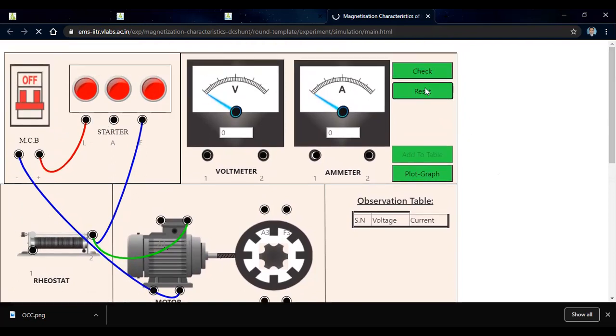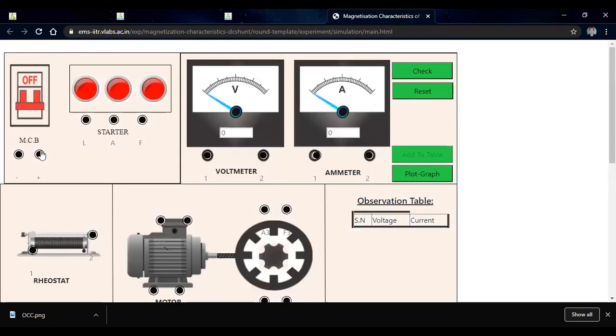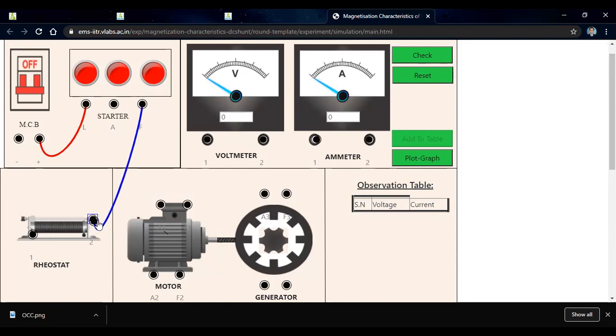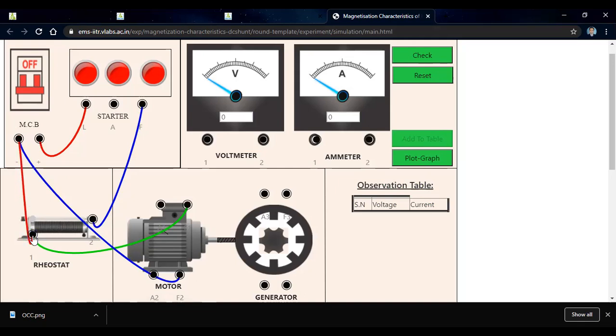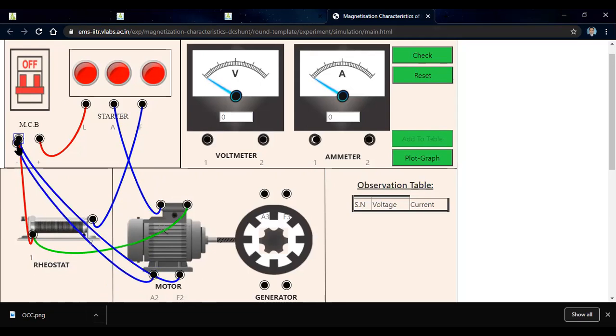Completing the motor connections: positive is connected to L, from the field point F it is connected to the MCB entering terminal, then from field we connect the rheostat and then to the field winding. The second part of the field winding is connected to the negative of the MCB. The starter A, armature terminal, is connected to the positive armature A1 of the motor, and A2 of the motor armature is connected to the negative of the MCB.